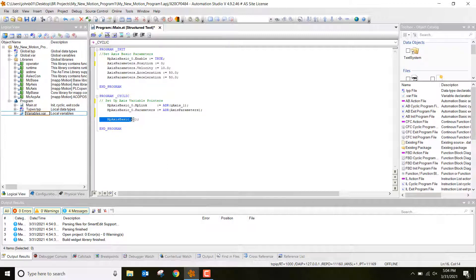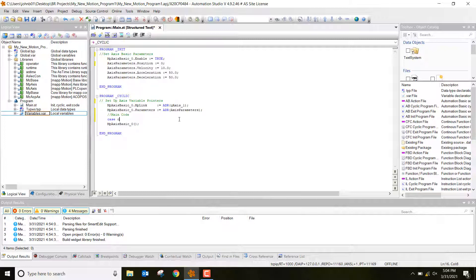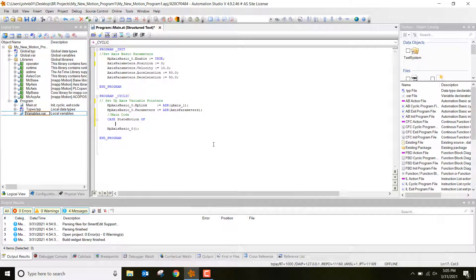This bottom part is the actual function block we're going to be calling — I want to call that once we're done writing the entire program. So right now I'm labeling this section 'main code.' Then we're going to do a case statement. We start with 'CASE state_motion OF' — you can hit Control+Spacebar and it will automatically populate that variable. State_motion is going to start with a value of zero, so our first case entry is zero colon.